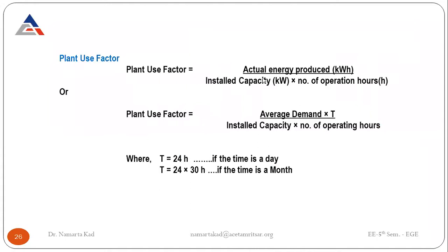Plant use factor equals actual energy produced divided by installed capacity of the plant multiplied by number of operating hours — how many hours the plant is in running condition. It is also calculated as average demand multiplied by T, divided by installed capacity and number of operating hours. Here T is 24 for daily purpose, or 24 into 30 for monthly calculation.